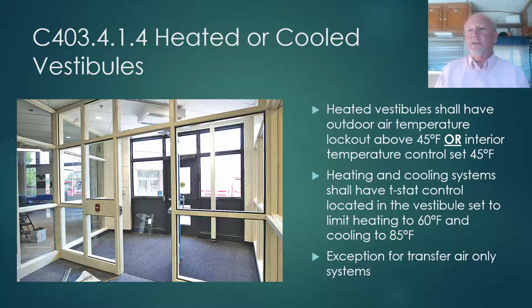If you have both heating and cooling systems supplying energy to the vestibule, then you shall have an independent control located in the vestibule that limits the heating to no higher than 60 degrees and the cooling to no lower than 85. And then finally, if you have no heating or cooling in the vestibule, it's not conditioned at all, that's fine. There's no change, nothing impacts you in the code. And if you use just transfer air, so if you transfer air through the conditioned space into the vestibule, air that would normally be exhausted or exfiltrated through the building, that's fine. You can still continue to do that, and there's no specific code requirement.